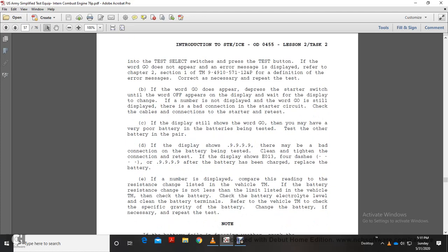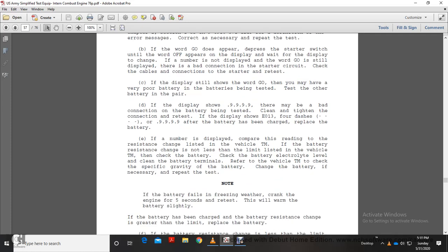Repeat the test. If the word GO does appear, press the start switch until the word OFF appears on the display. Wait for the display to change. If the number does not display and the word GO is still displayed, check the connection to the start circuit and the cable connection to the start, then retest. If the display still shows the word GO, it may have a very poor power battery. Test the battery and repair.